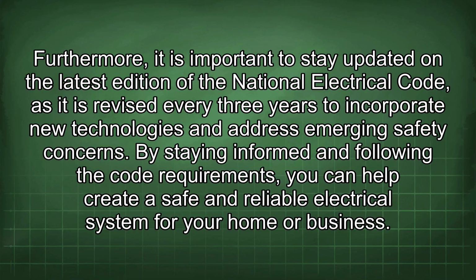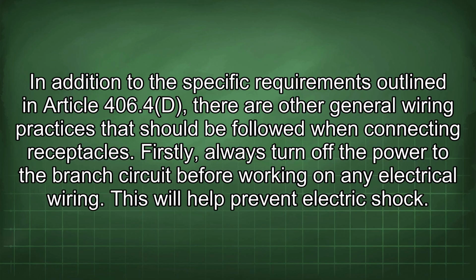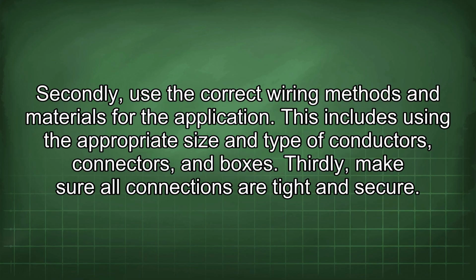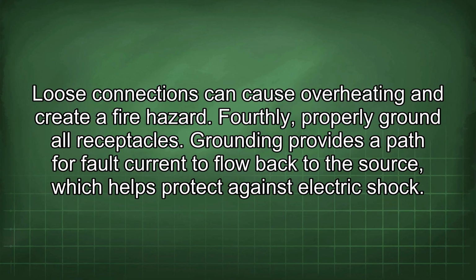home or business. In addition to the specific requirements outlined in Article 406.4(D), there are other general wiring practices that should be followed when connecting receptacles. Firstly, always turn off the power to the branch circuit before working on any electrical wiring. This will help prevent electric shock. Secondly, use the correct wiring methods and materials for the application. This includes using the appropriate size and type of conductors, connectors, and boxes. Thirdly, make sure all connections are tight and secure. Loose connections can cause overheating and create a fire hazard.